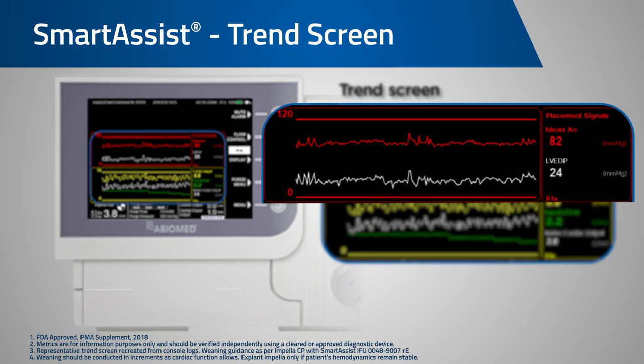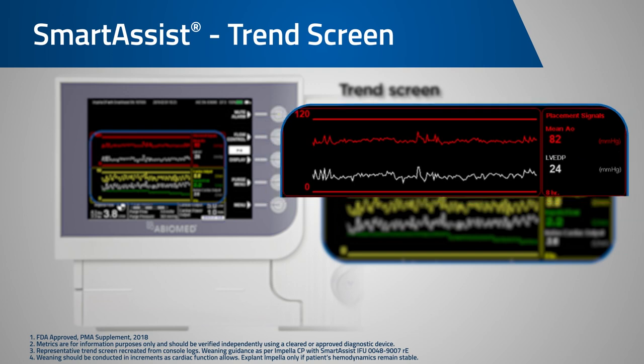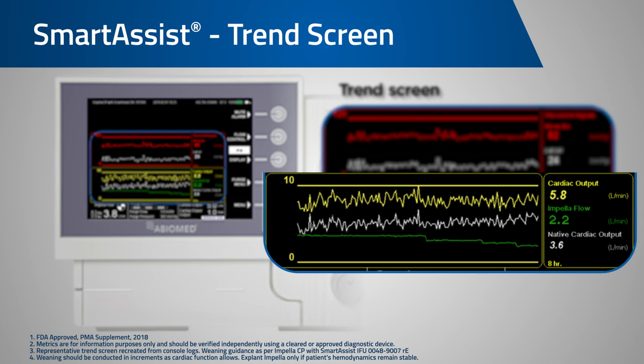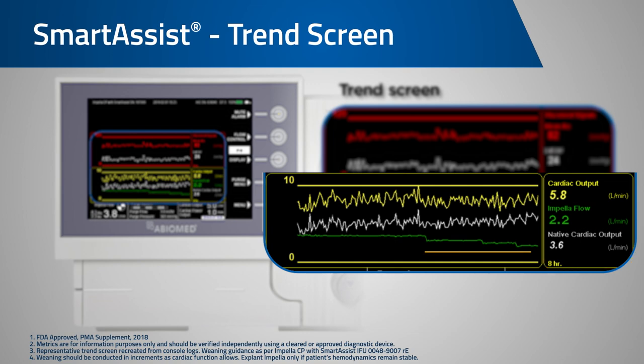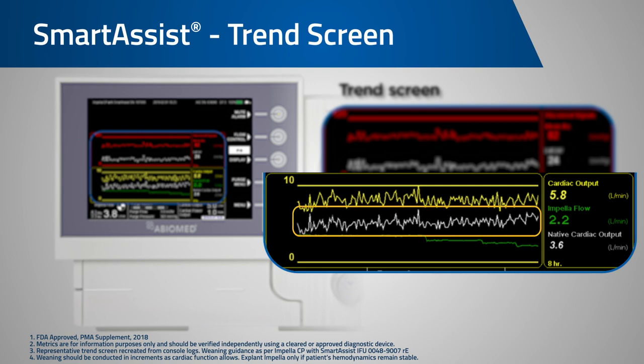The red placement signals box now displays a trend of mean arterial pressure as well as the LV load, labeled LVEDP, over time. The bottom yellow box is the breakdown of cardiac output. After a reference cardiac output is entered, our console provides the contribution from the Impella pump and the native heart to the total cardiac output. The green waveform is the cardiac output delivered from Impella flow and the white waveform is the estimated native contribution to cardiac output.